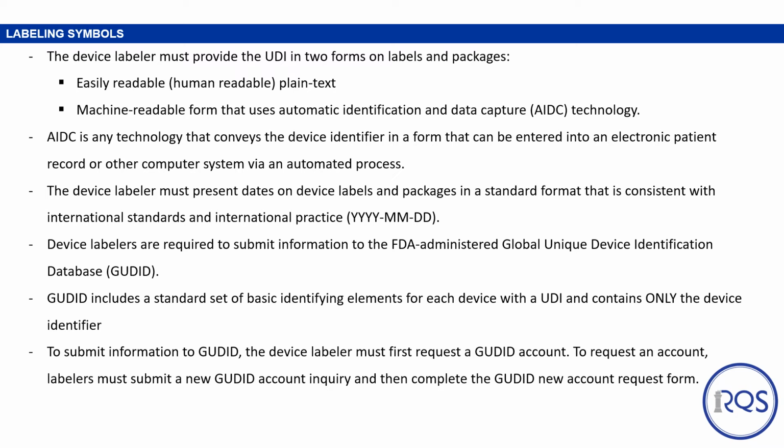The device labeler must also present dates on the device labels and packages in a standard format that is consistent with international practices and standards. This includes 4 digits for the year, 2 digits for the month, and 2 digits for the date.